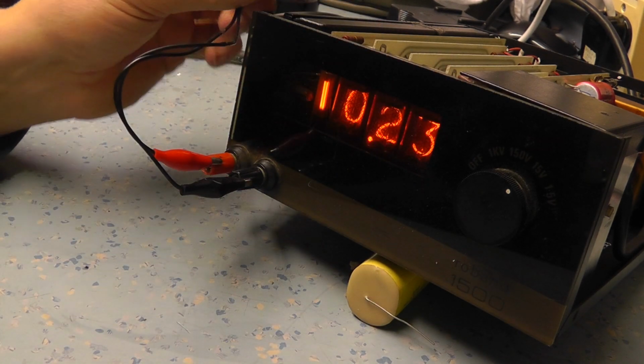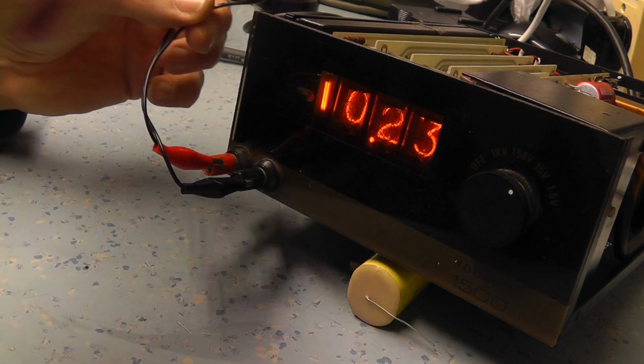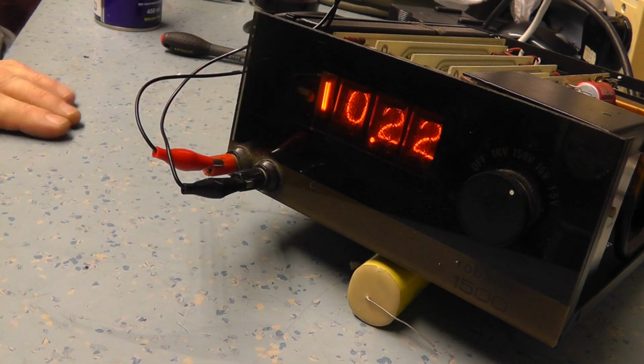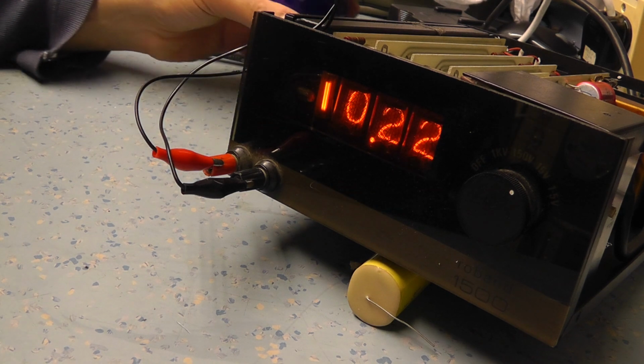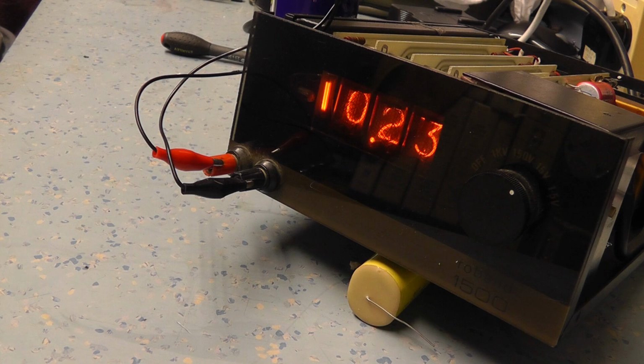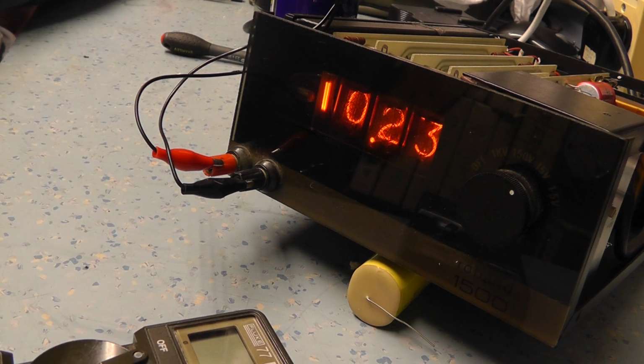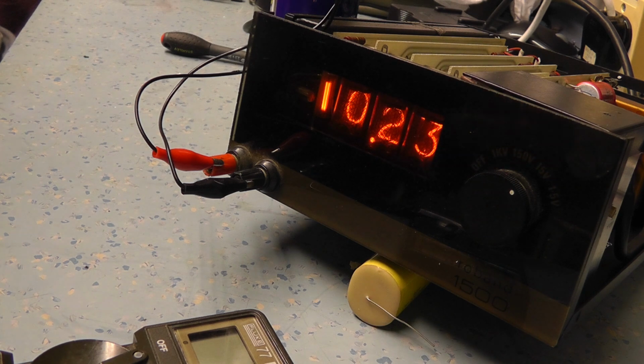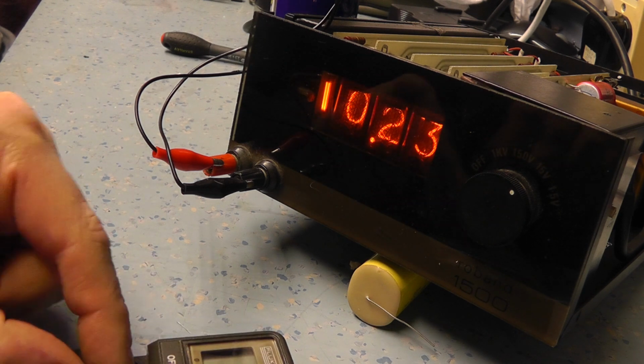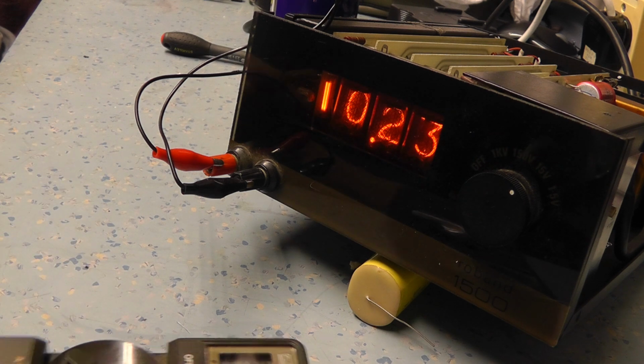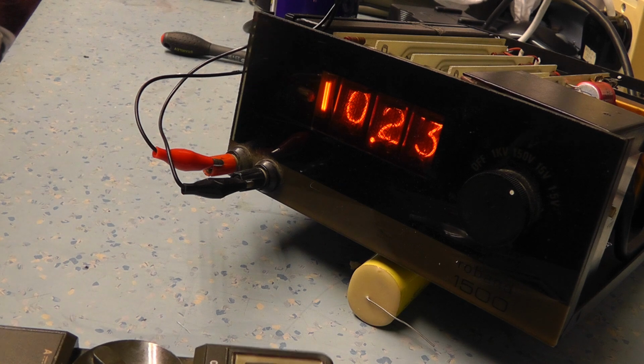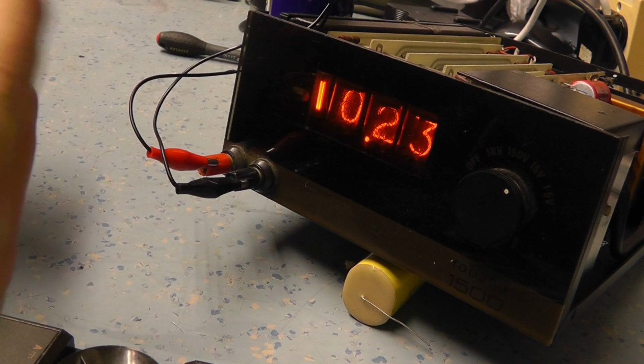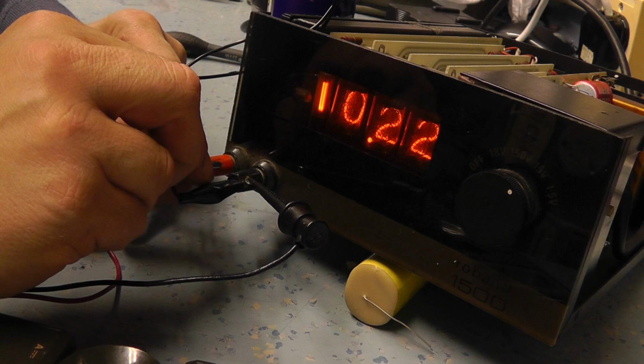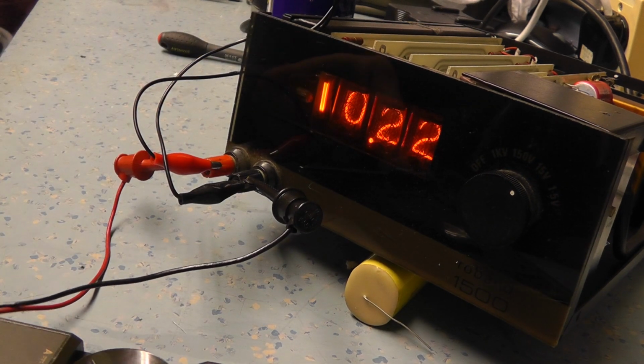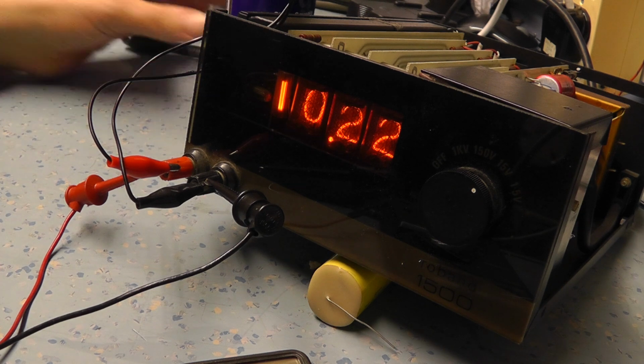And that says 10.23 volts, okay, which I think is overreading slightly. Let's get that out of the way. I don't want that in the view of the camera. So 10.22 volts. So what we'll do is we'll get our Fluke multimeter and connect that to the front panel and see what we're actually putting into the unit. But it certainly looks like it's within the ballpark. It's probably never been calibrated, this meter, and I'm not sure of the original accuracy of these meters anyway, but it's probably sort of 0.5%, something like that. So let's see what we're putting in with my Fluke. Let's just hook this up. Okay, I'm putting in 9.98 volts and it's showing 10.22.